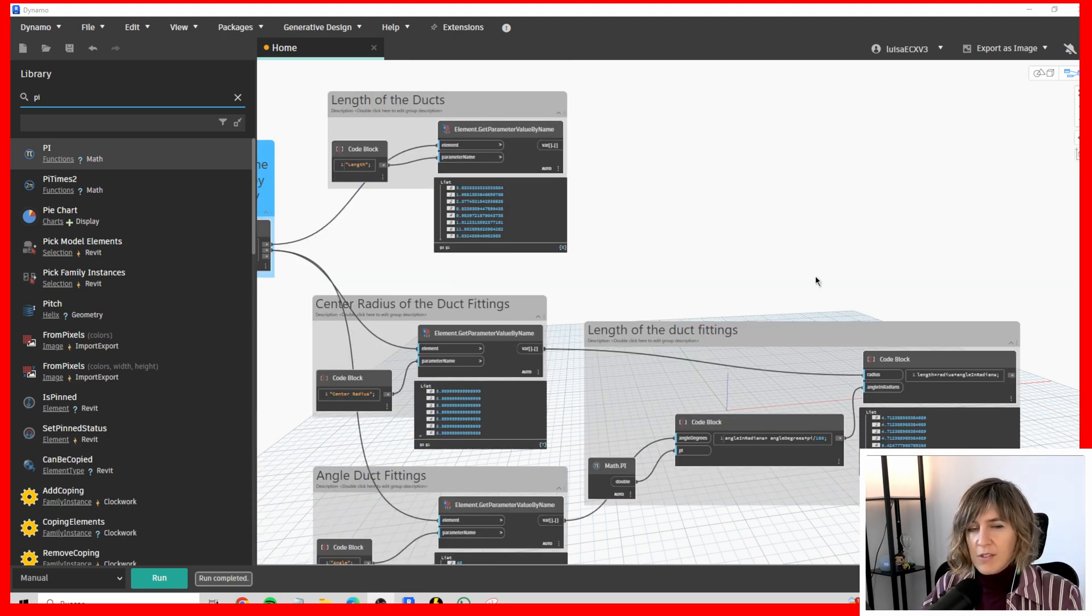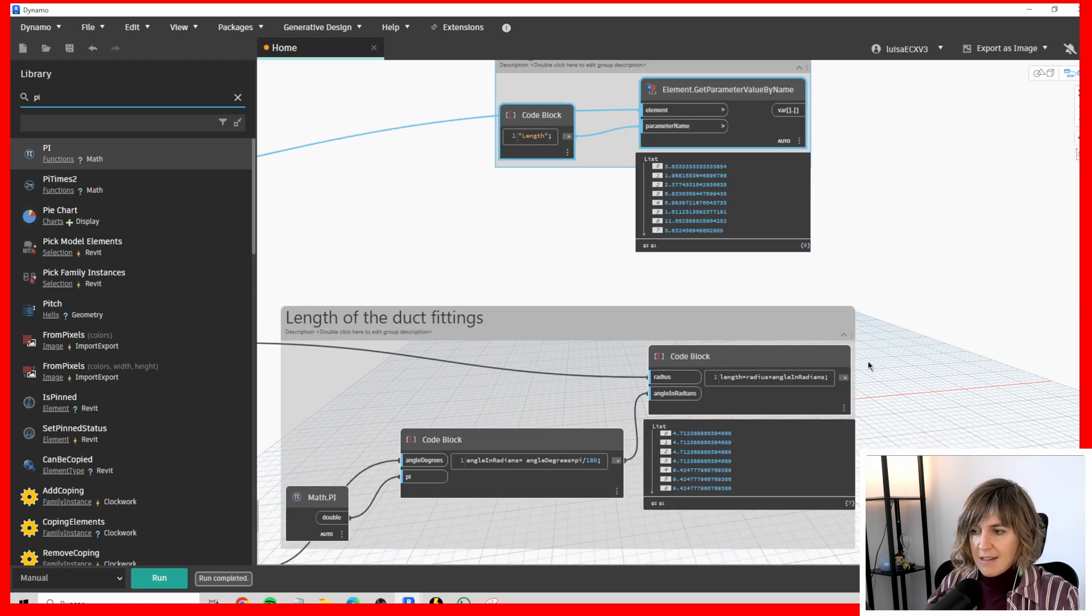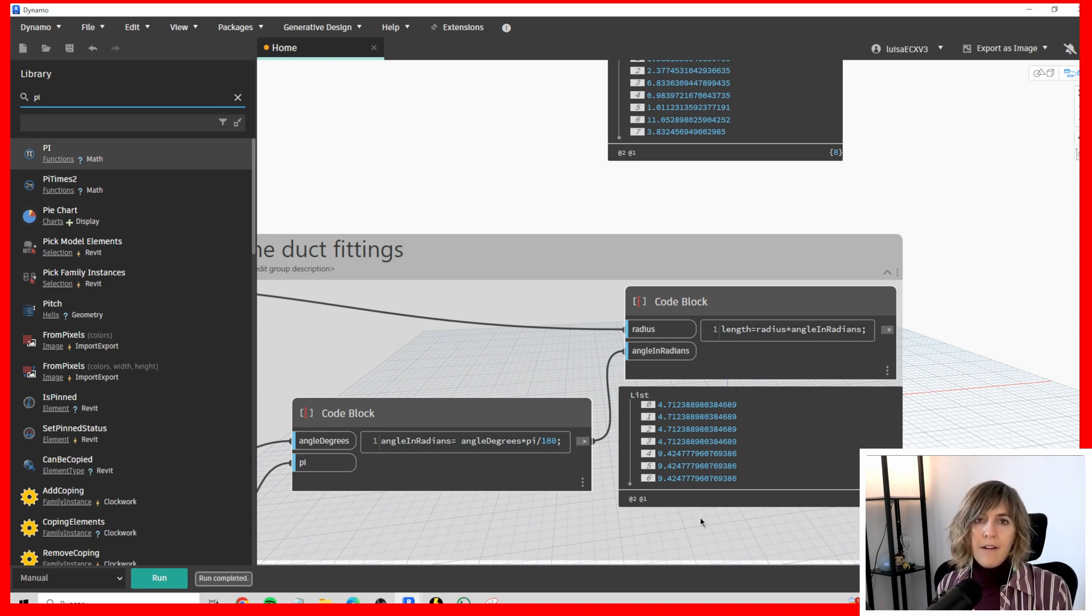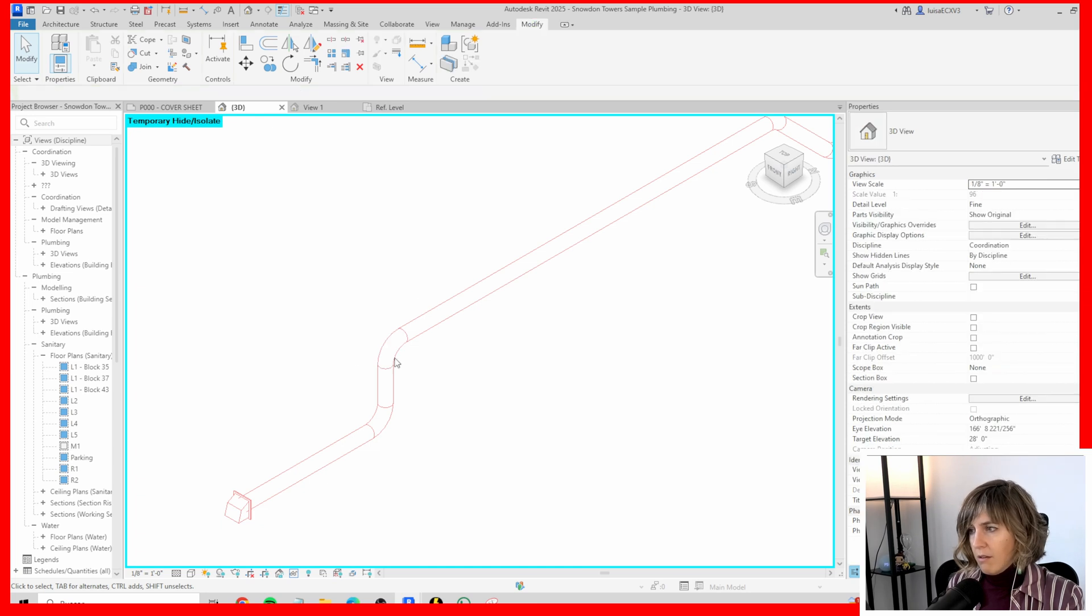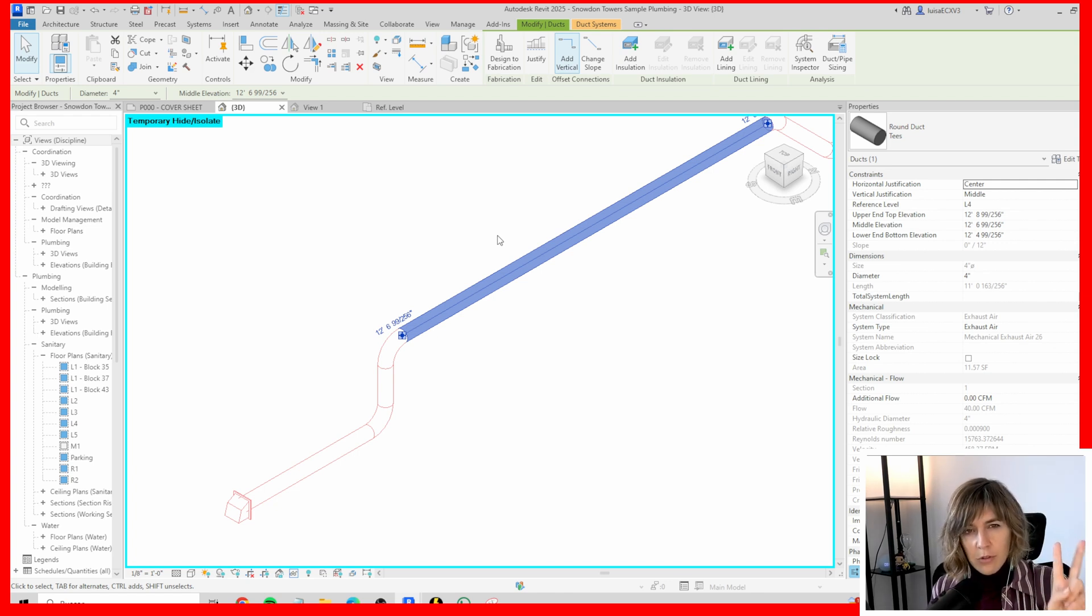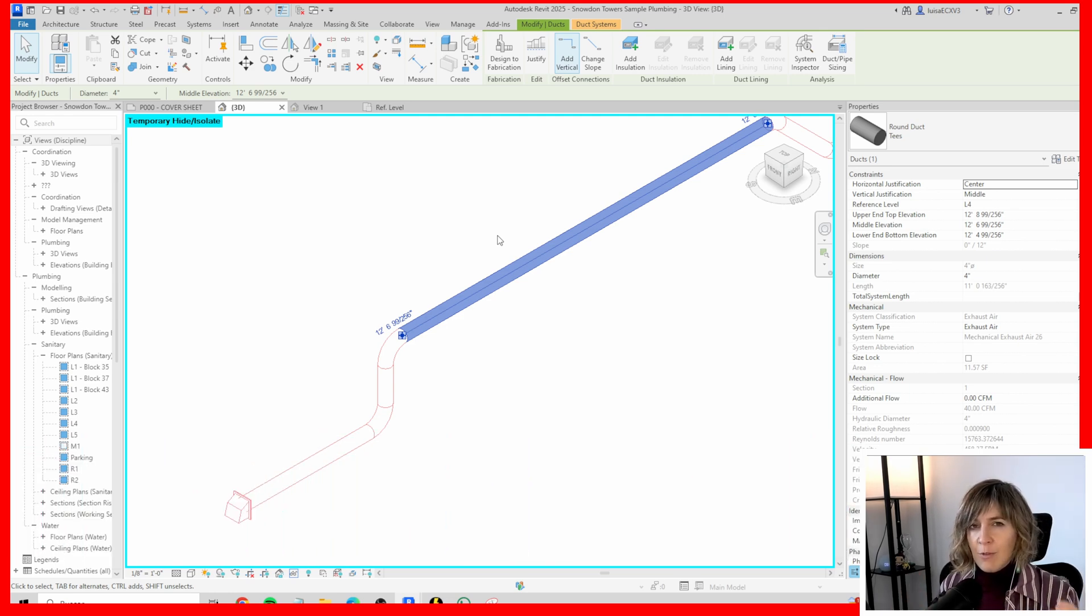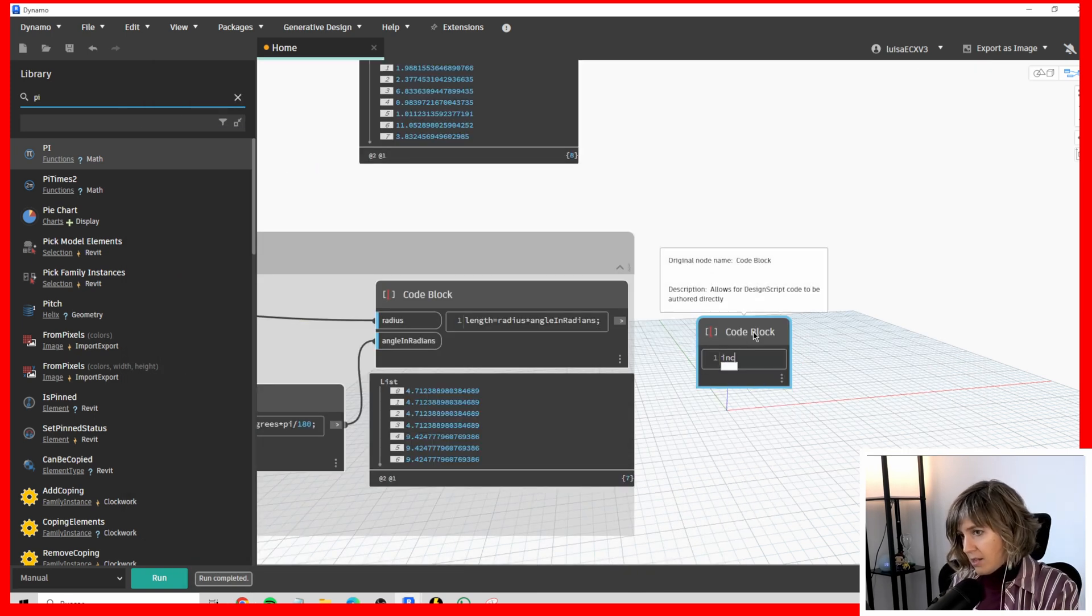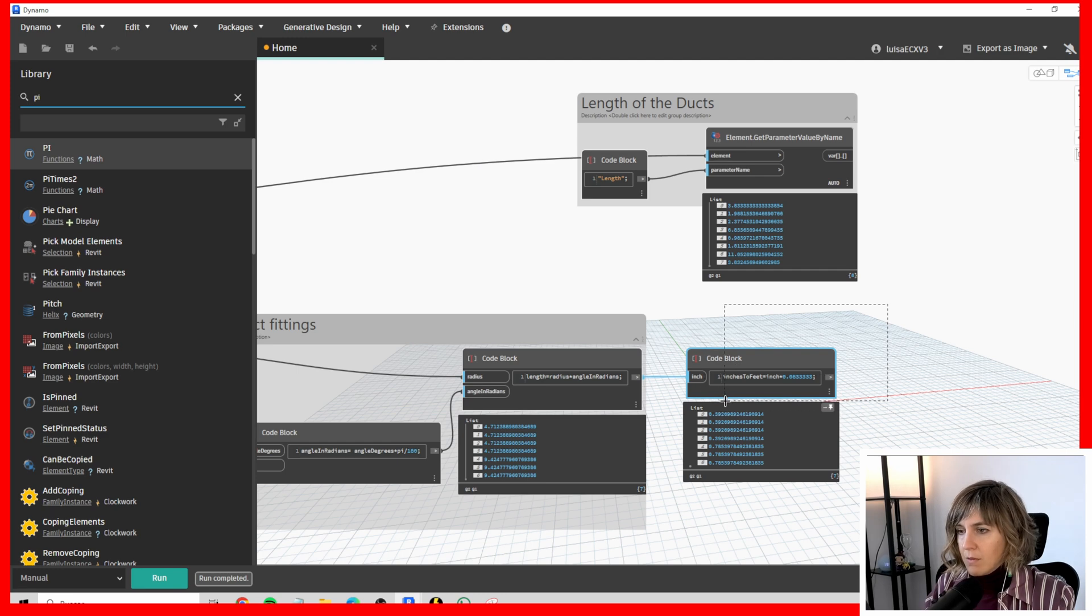Which units are we using here? As you can see here in the ducts we have 3.83, 1.98, however in the duct fittings we have 9.42 which is bigger. But it doesn't make sense because normally the duct fittings are smaller than the duct. Perhaps the problem is in the units. Here if I go to a duct fitting I can see this is measured in inches. However, I have the length of the ducts in feet. We have two different units that we have to consider when working with Dynamo. I'm going to be converting the inches to feet. An inch is 0.0833333 feet. Inches to feet equals inch per this. That does look way better when considering the units.